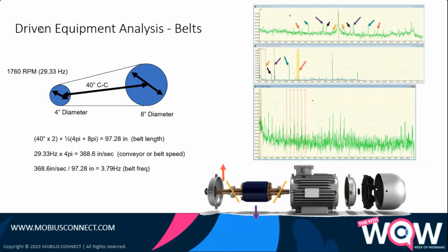Now, if we take a look at another electric motor-driven system, just a belted fan application, I can look at belt tensioning. Belt tensioning has a direct impact. The number one thing that we always find is that belts are over-tensioned, not under-tensioned. Why? Because with turbulence, things flap a little bit at the bottom. So as a result, you go, oh, that flapping must mean it's loose, tighten it up some more. Or worse, people follow the belt tensioning tables.